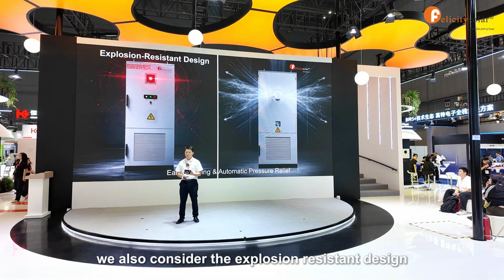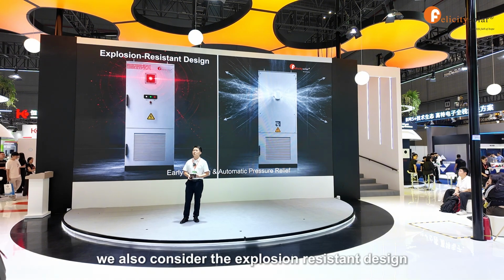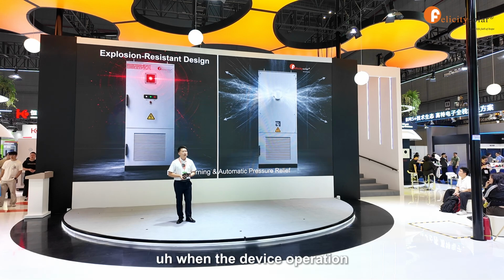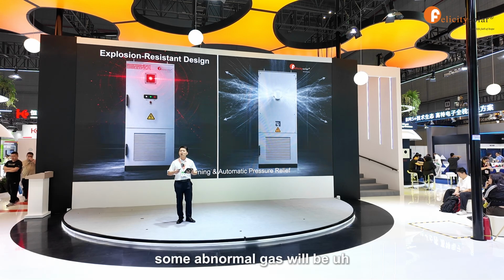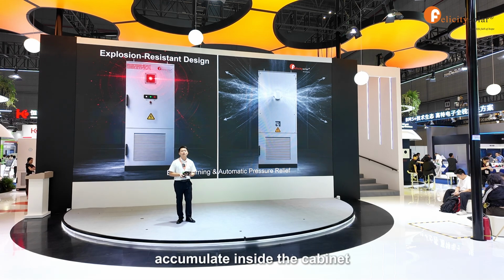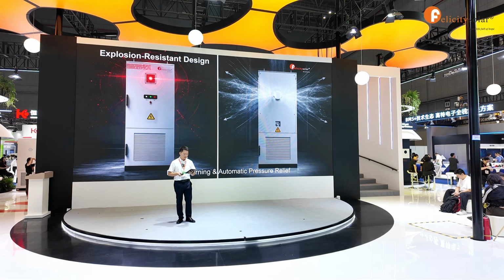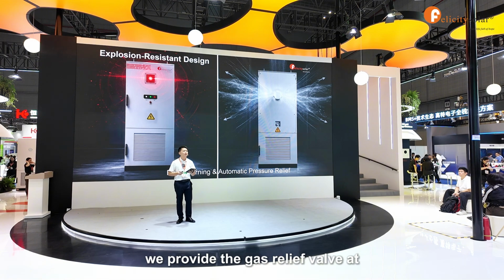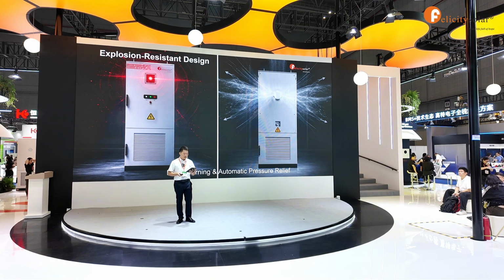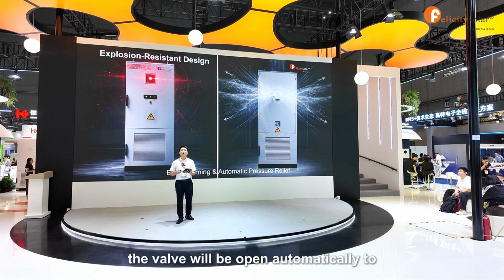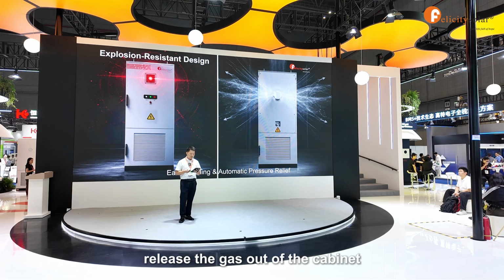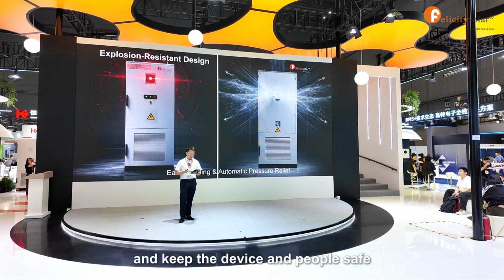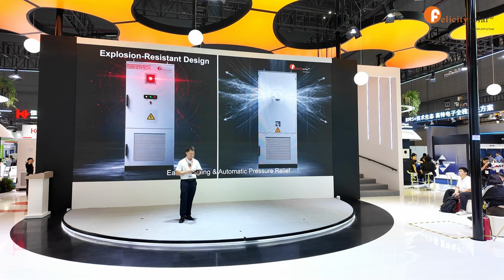About safety, we also consider the explosion resistant design because, as we all know, when the device operates, abnormal gas will accumulate inside the cabinet and the pressure will become higher. So considering such a situation, we provide a gas relief valve at the backside of the cabinet. And when the valve detects the pressure is very high, the valve will open automatically to release the gas out of the cabinet and keep the device and people safe.